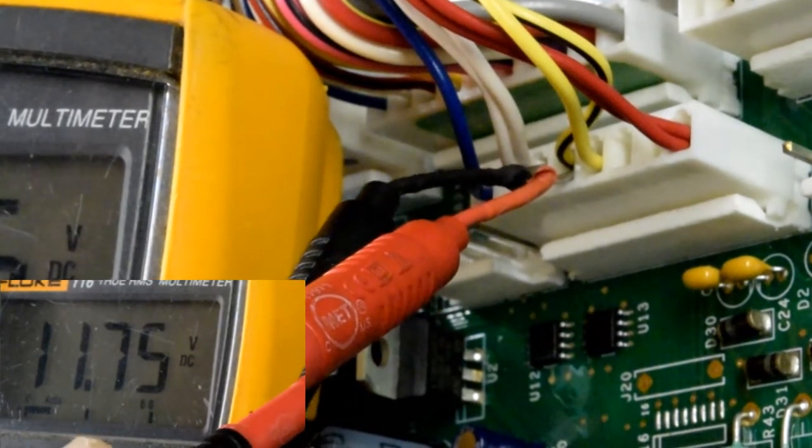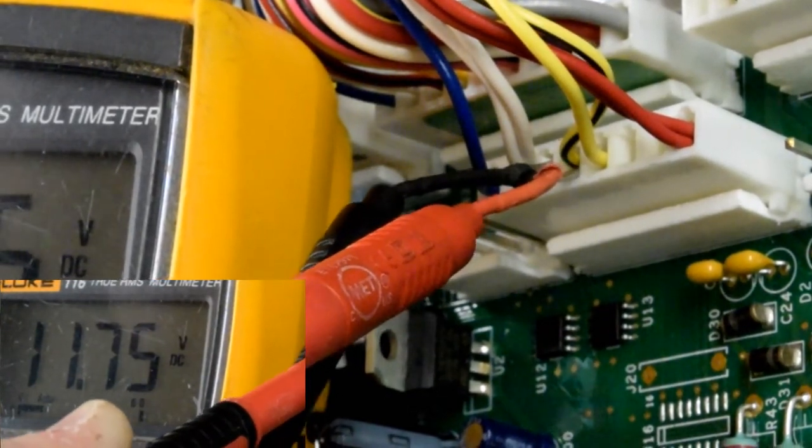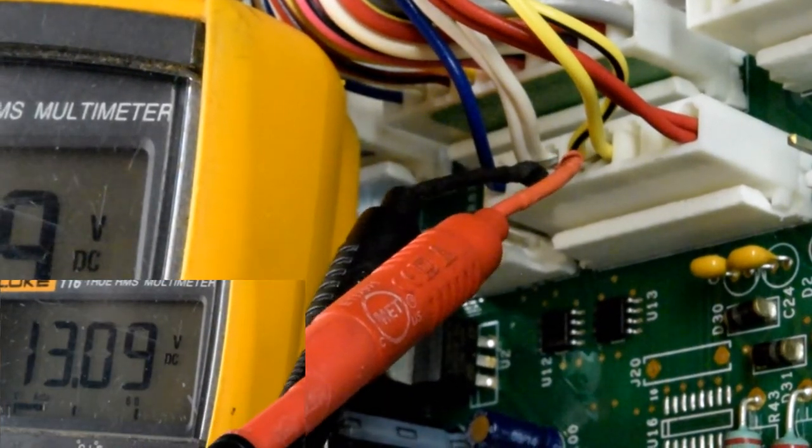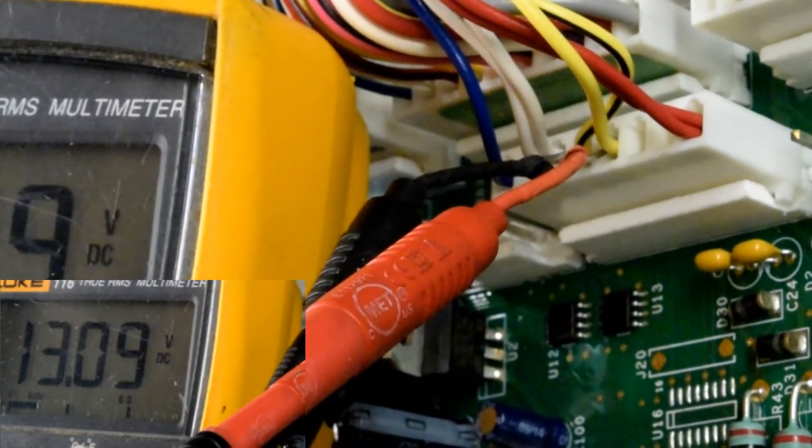The next test is the condenser fan motor. Again, leave the black where it's at, move the red to the right one pin slot. Now you're on pin number 5 - should read between 12 and 14 volts.